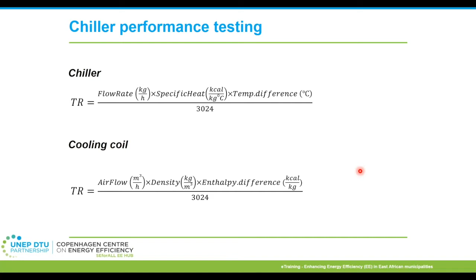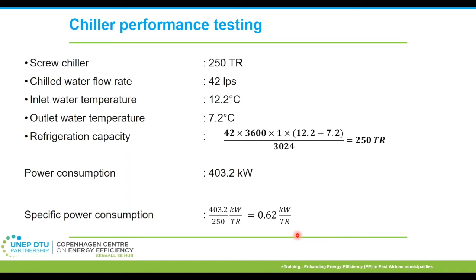Based on the TR that is evaluated and the power consumption measured, they arrive at the specific power consumption. This is just an example for your reference. You can use the conversion formulas shared in previous slides to convert this specific power consumption value into a COP or energy efficiency ratio.